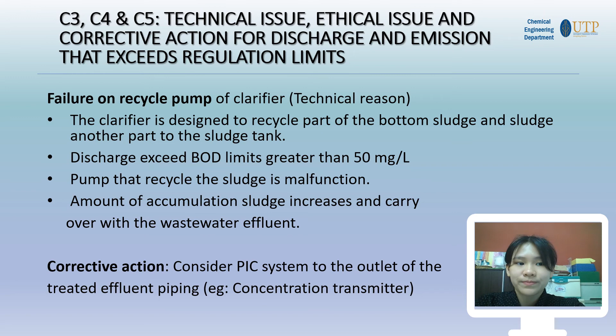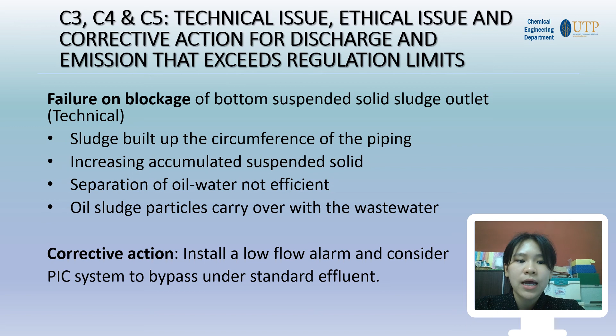The second technical issue is due to the blockage at the bottom outlet of the oil-water separator. Oil sludge that is supposed to flow out from the separator builds up on the piping circumference and blocks the sludge exit. This will increase the amount of accumulated suspended solids until the sludge particles are carried together with the wastewater effluent. Corrective action for this incident is to install a low flow alarm at the sludge outlet to notify the operator for pipe cleaning, as well as a process instrumentation and control system that opens the bypass valve so that the contaminated treated wastewater will be recycled back into the system.